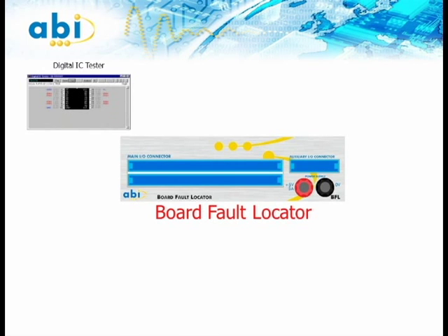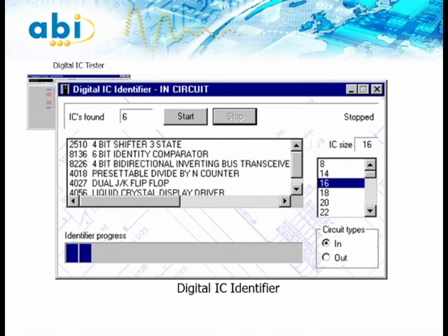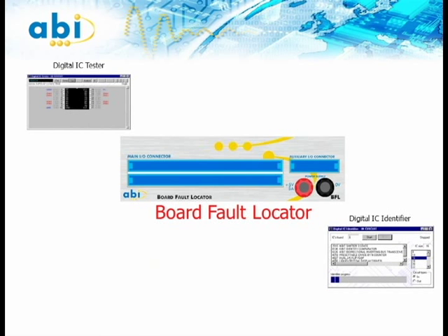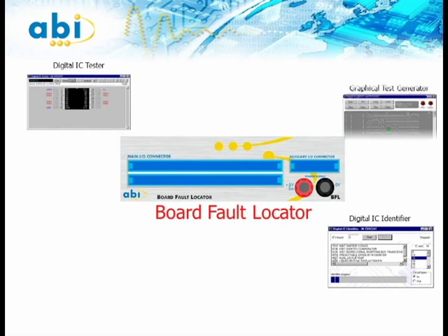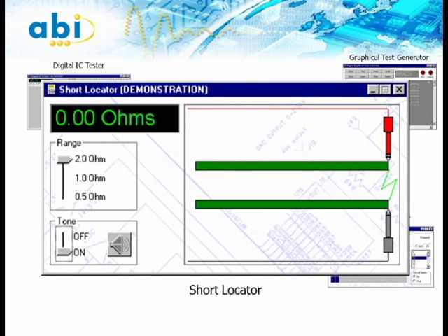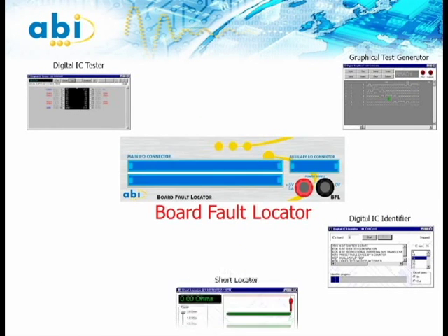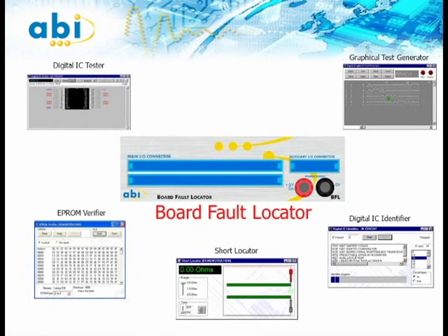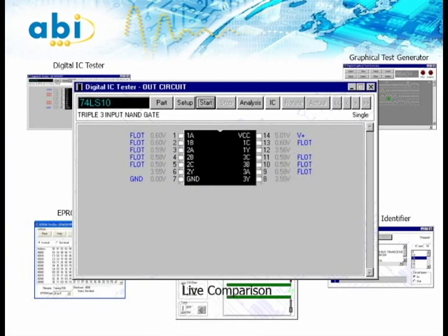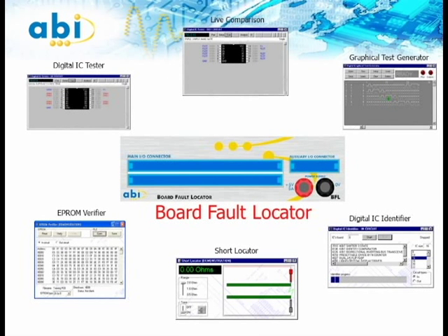Other features available in the module include the IC identifier, which is used in cases when IC numbers are unknown, cannot be read, or recognized. The graphical test generator is for more advanced users, allowing them to design custom functional tests. With the graphical test generator, BFL offers access to each test channel with read and write options in order to monitor the response from the board under test. The short locator allows the user to detect the proximity of a short on a board. The EPROM Verifier offers the possibility to read and verify EPROMs in and out of circuit, and allows two identical boards to be powered and compared at the same time.